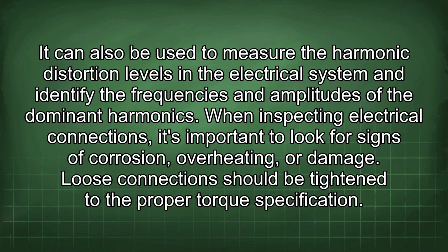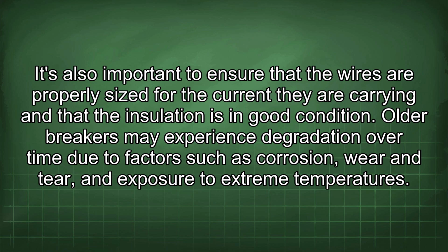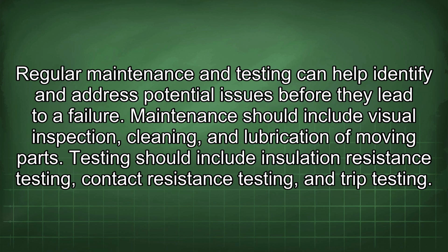When inspecting electrical connections, it's important to look for signs of corrosion, overheating, or damage. Loose connections should be tightened to the proper torque specification. It's also important to ensure that the wires are properly sized for the current they are carrying and that the insulation is in good condition. Older breakers may experience degradation over time due to factors such as corrosion, wear and tear, and exposure to extreme temperatures. Regular maintenance and testing can help identify and address potential issues before they lead to a failure. Maintenance should include visual inspection, cleaning, and lubrication of moving parts. Testing should include insulation resistance testing, contact resistance testing, and trip testing.